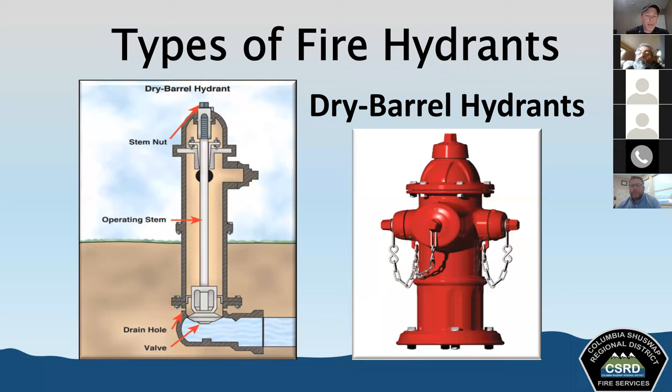And each outlet has to be capped or have a hose attached before opening that. If we leave the cap off and don't attach a hose to it, water's just gonna come pouring out and it's not gonna be doing us any good. We're now draining our own system and reducing the amount of water we have to put out the fire. So we have to be very careful. One other thing we should always be careful of when we're working with dry hydrants is, when we shut it down, we want to leave the caps off for a little bit of time before we put them on.